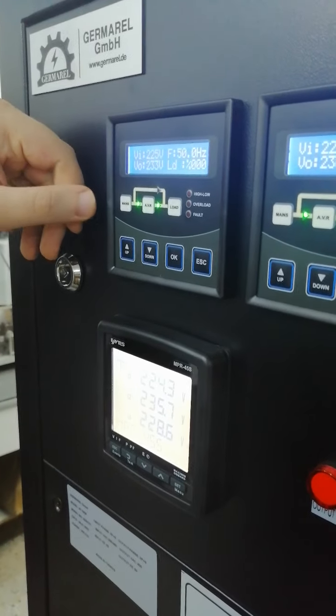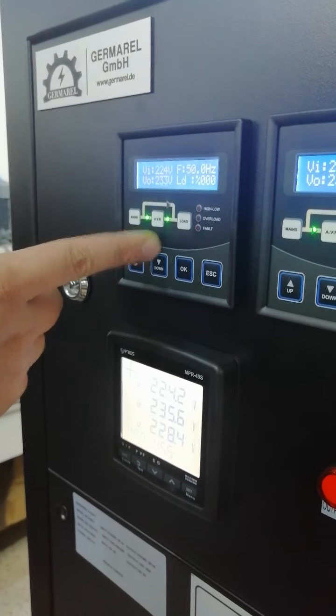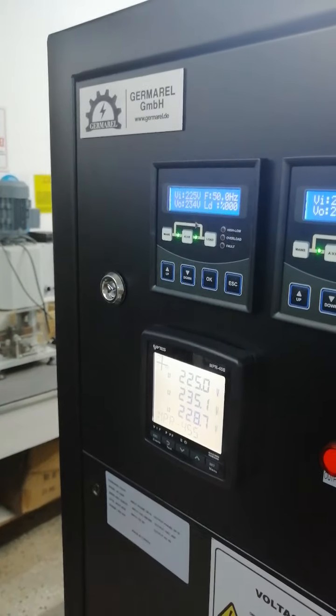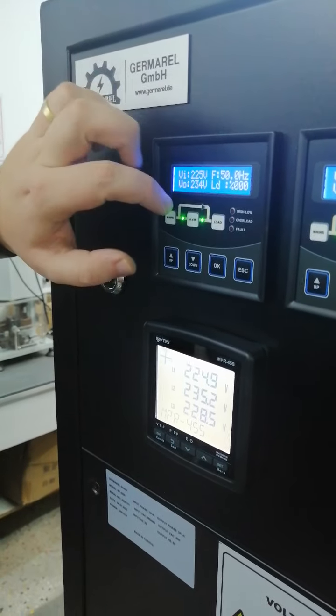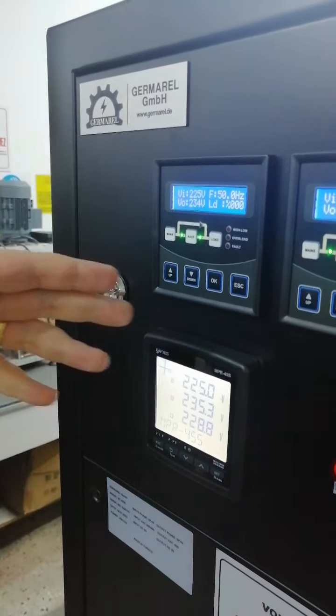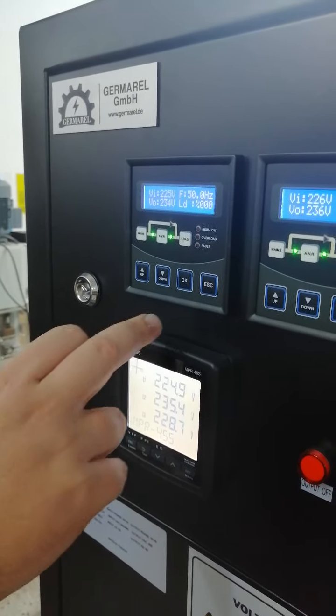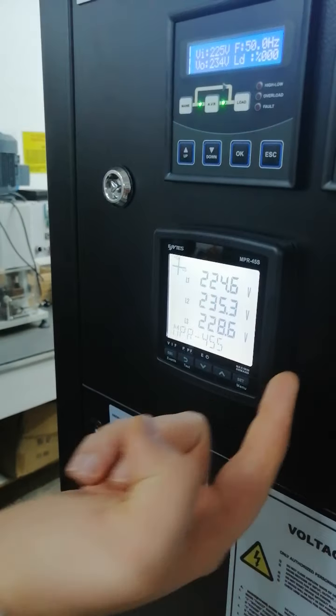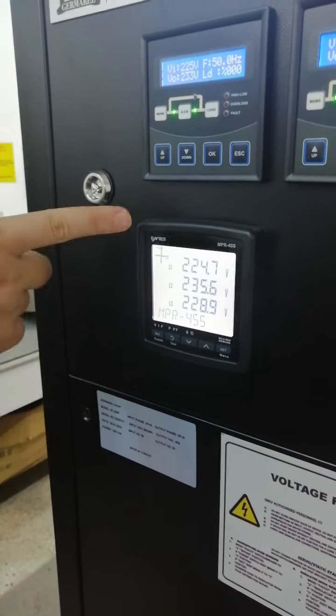On the block diagram you can see each part: mains, AVR — AVR means the device — and load. Green lights tell us everything is going well. We also have three alarms on the panels: high voltage, low voltage, overload, and a general fault alarm.